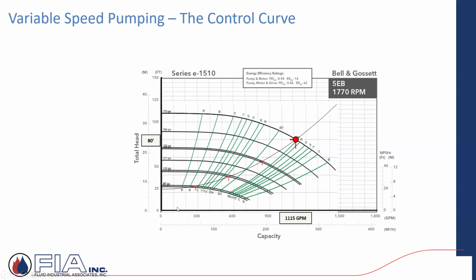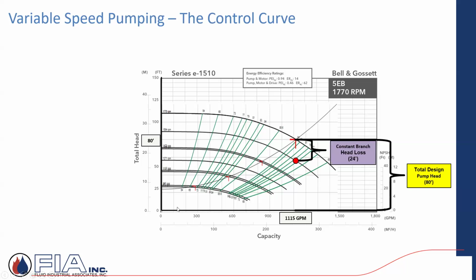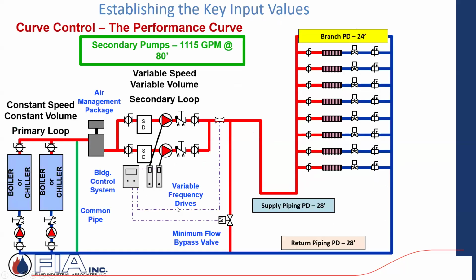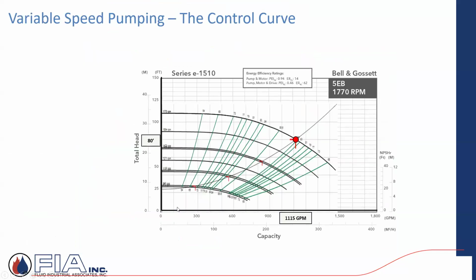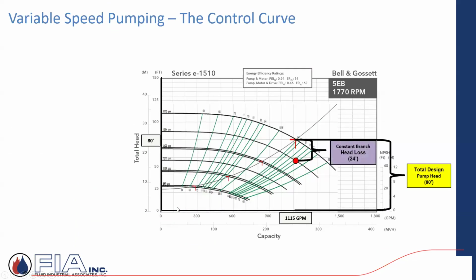So if I look at that curve of the 1115 at about 80 feet of head, there's my total design. But in reality, I have a constant pressure drop, that 24 feet, which was this guy up here. It's the pressure drop of the terminal, the control head, the balance valves, 24 feet. I want to maintain that minimum. So I have a variable distribution head loss of 56 feet of head.